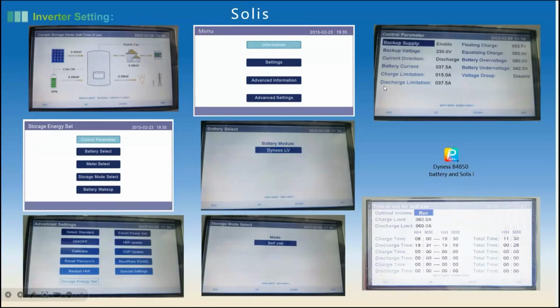As long as you can see the charge and discharge current limit, that means the battery and the inverter communication is normal. For example, we use one BX51100, the maximum discharge current limit is 100. When we connect two batteries in parallel, the maximum discharge current limit should be 200. But if we can only see 100, that means one of the batteries is not communicating with the inverter properly. So in these cases, we need to check whether the battery dip switch setting is correct, and whether the communication cable between battery and battery is correct.